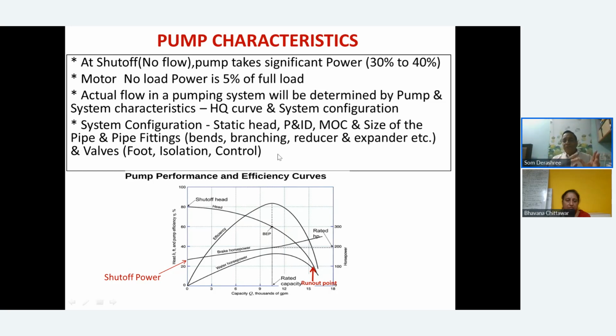So system configuration decides the system head, which again depends on the flow, as we know. Each manufacturer will give you, at this particular flow and this particular valve position, what the delta P, the pressure drop across the valve, is. So accordingly, you can draw your system curve.